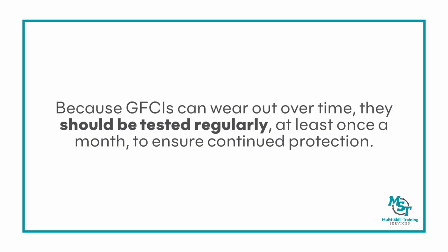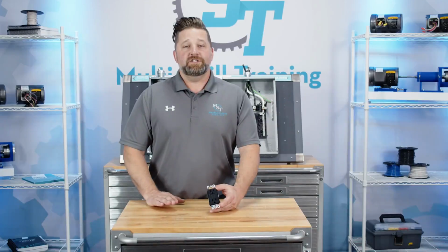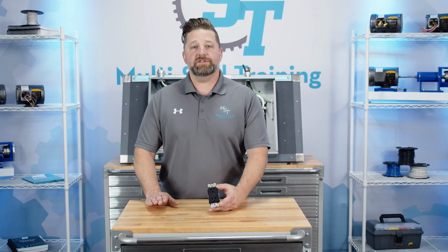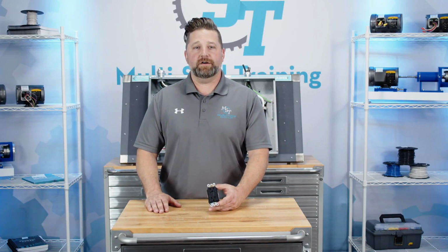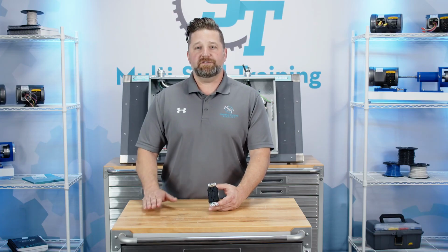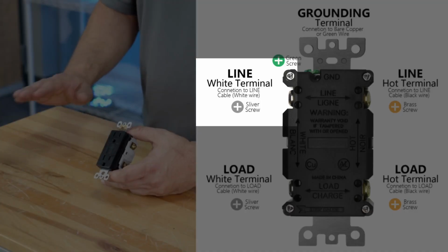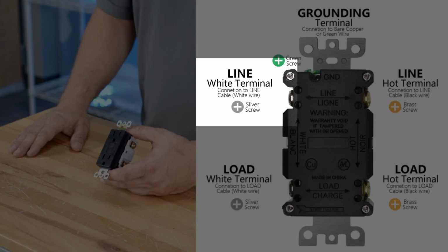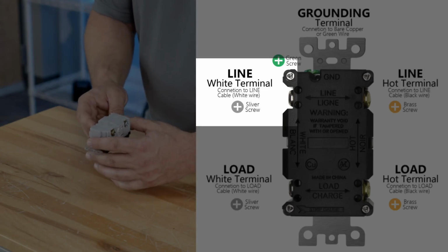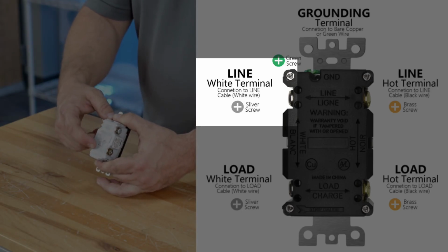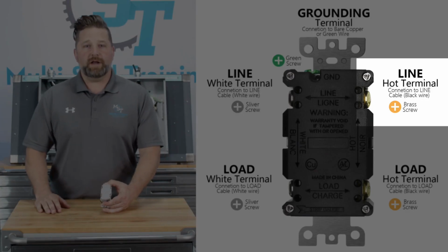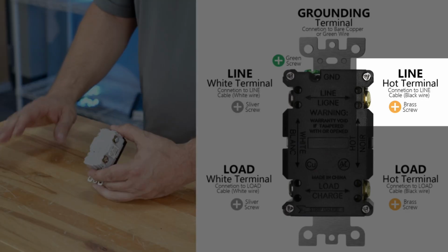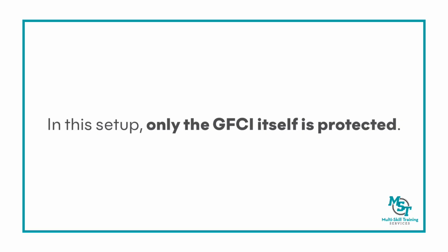Because GFCIs can wear out over time, they should be tested regularly, at least once a month, to ensure continued protection. GFCI outlets can be wired in 2 ways, depending on the level of protection desired. In the first method, the GFCI protects only itself. The white neutral wire connects to the silver screw labeled line. As you can see on the back, it's labeled line here on the bottom. While the black or red hot wire connects to the brass screw, also labeled line. In this setup, only the GFCI itself is protected.